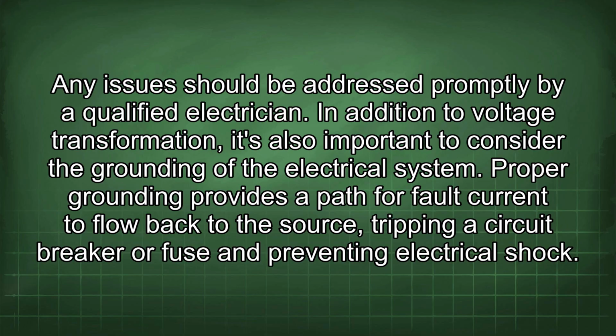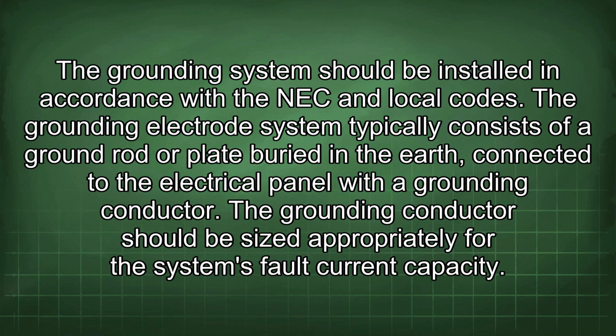In addition to voltage transformation, it's also important to consider the grounding of the electrical system. Proper grounding provides a path for fault current to flow back to the source, tripping a circuit breaker or fuse and preventing electrical shock. The grounding system should be installed in accordance with the NEC and local codes. The grounding electrode system typically consists of a ground rod or plate buried in the earth, connected to the electrical panel with a grounding conductor. The grounding conductor should be sized appropriately for the system's fault current capacity.